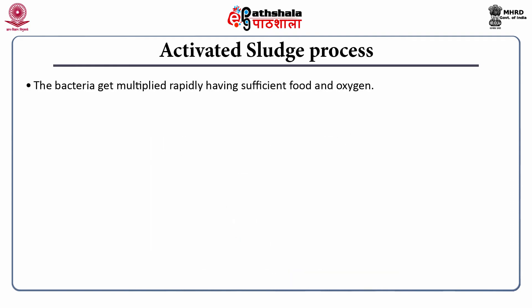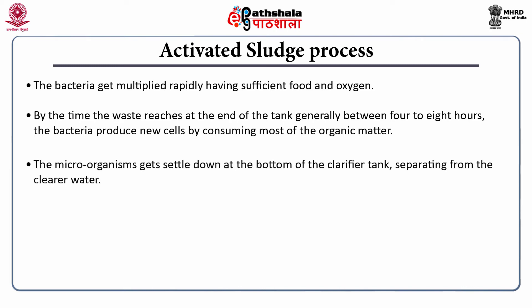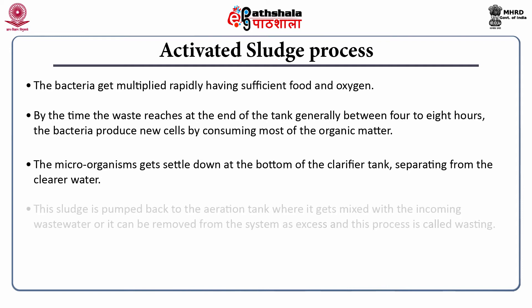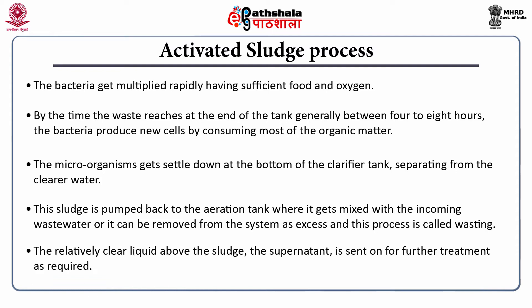In the activated sludge process, bacteria get multiplied rapidly with sufficient food and oxygen. By the time the wastewater reaches the end of the tank — generally between 4 to 8 hours — the bacteria produce new cells by consuming most of the organic matter. The microorganisms settle at the bottom of the clarifier, separating from the clear water. This sludge is pumped back to the aeration tank or can be removed from the system as excess — a process called wasting. The relatively clear supernatant is sent on for further treatment.